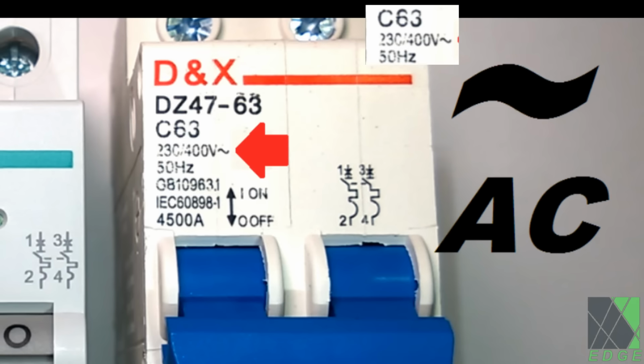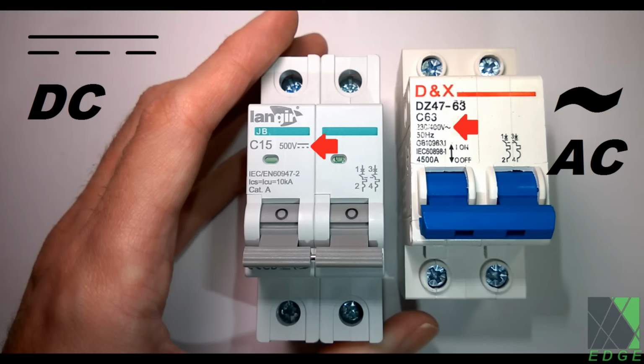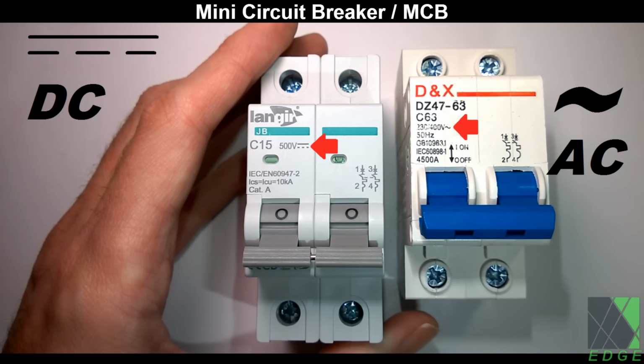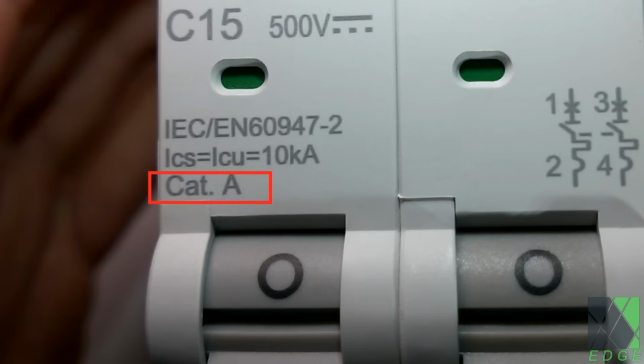On the right we have the symbol that looks like a wavy line, the symbol for AC or alternating current. This is an AC breaker and not suitable for DC. This type of circuit breaker is actually called a mini circuit breaker or MCB, but there are a lot of classes and variations of each type, so it's important to pay attention to the details. For example, here we see this circuit breaker is rated for fast trip, meaning it's sensitive to overcurrent and easily trips. I prefer this type, but sometimes you would want a brief delay.